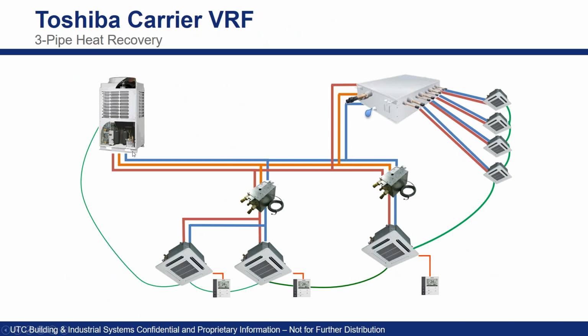So this is a good diagram here of our 3-pipe, and that we're showing liquid, suction and hot gas lines going to our flow selector boxes. This is actually a good image of our single port boxes, showing this single port feeding 2 4-way cassettes. So figure you got a large conference room or just a large multi-use space. You can feed 2 fan coils off of 1 flow selector.